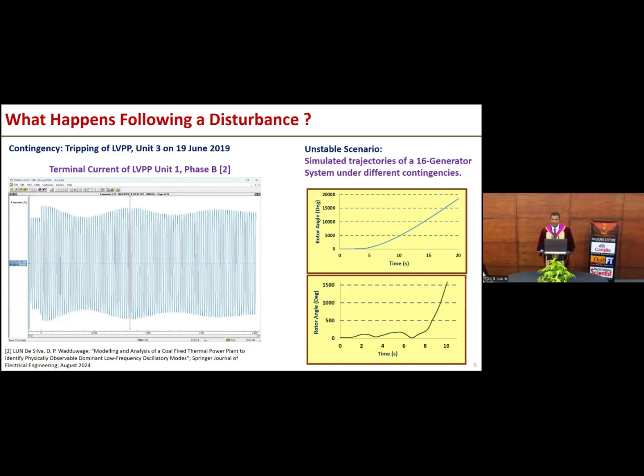And I'm showing here two graphs where you can see rotor angle versus time under two different cases coming out of the simulations of the 16 generator system without adequately modeling the relevant protection schemes. So speed is the rate of change of rotor angle, so the same information will be visible in the speed also. In the first scenario, you will see the angle increases indefinitely in the first swing, which is known as first swing transient unstable scenario.